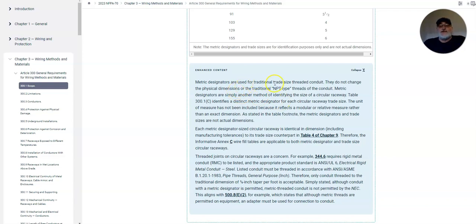Metric designators are used for traditional size threaded conduit. They do not change the physical dimensions or the traditional NPT threads of the conduit. Metric designators are simply another method of identifying the size of a circular raceway. Table 300.1(C), which is the one that we just looked at, identifies a distinct metric designator for each circular raceway trade size. What does that mean? It's a lot of words. What we're talking about is just basically the conduit themselves. Okay, just like we kind of covered.